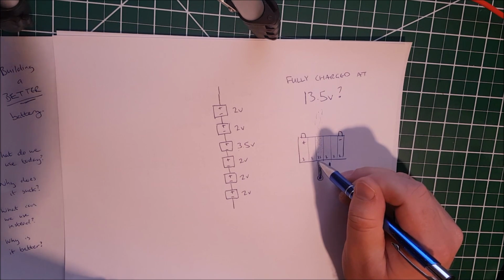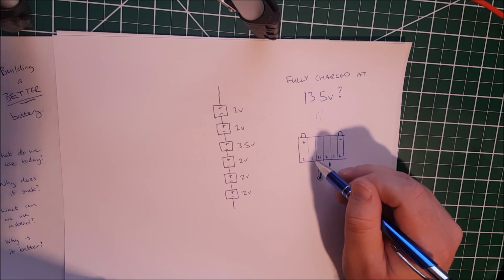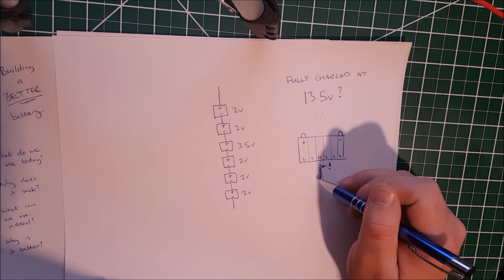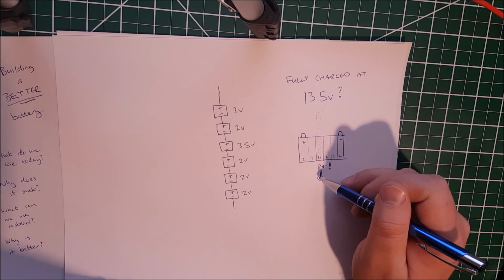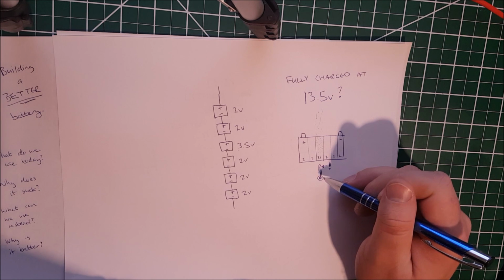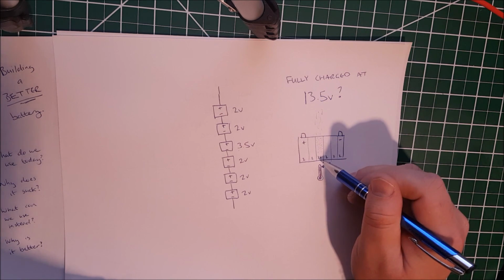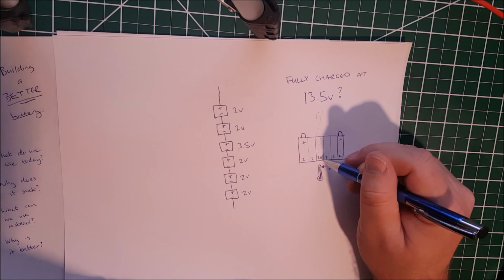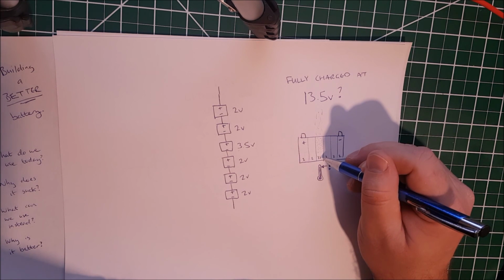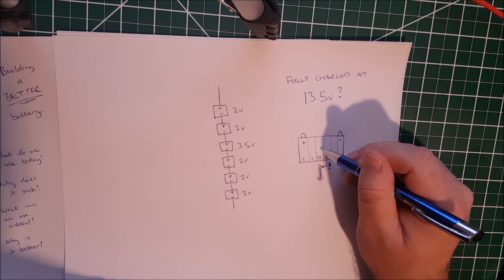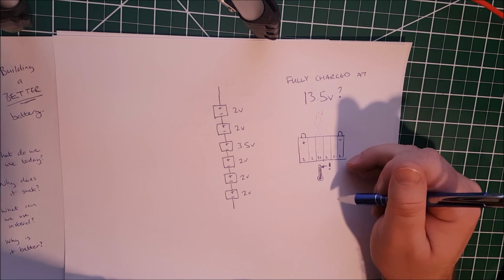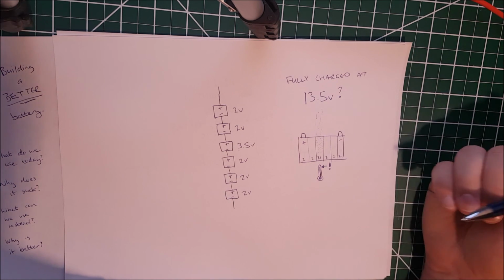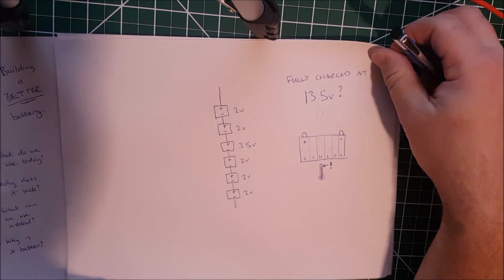So in this case, this one cell is overcharging. It could have been damaged because it was dropped. It could have been damaged from heat. And maybe the battery is just aging. Either way, at this point, the cell is getting hot. You're wasting energy because you're just producing heat here, and you're also producing hydrogen in a lead acid battery, which could ignite if it came into contact with a spark.